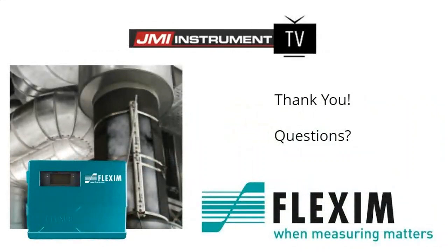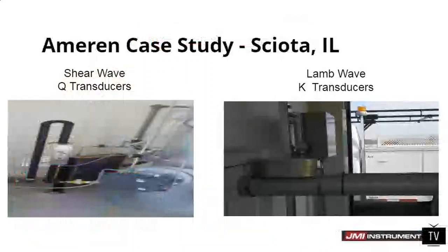Sorry, the other thing I wanted to talk about, since I have time here, is typical applications. The other common applications we have with gas would be odorizer pacing. A lot of companies use us to pace their odorizers. Then there are distribution or compressor stations, where they're monitoring gas coming into the station and gas leaving the station. And on pipelines, we see a lot of check metering, where a customer is getting gas from another pipeline company. The provider has a custody transfer meter, and then the consumer will use a Flexim meter as a check meter to make sure that they're not being overbilled.